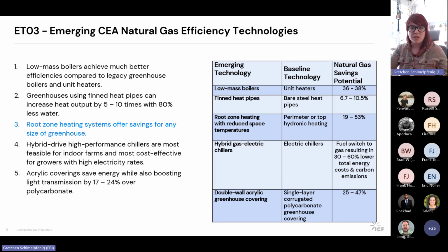And so a manufacturer has demonstrated savings of 6 to 11% compared to a bare steel heat pipe, but we find that there could be even additional savings because there's not yet much study there. And this is because 5 to 10 times heat output with 80% less water should result in increased gas savings. I'll just note that the manufacturer was comparing their generation 1 finned heat pipe to their most recent generation of finned heat pipe. There's actually not a study comparing bare steel heat pipes to finned heat pipes. This should be a conservative energy savings estimate.